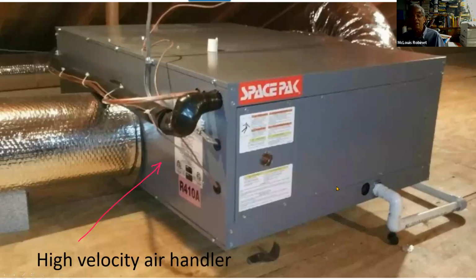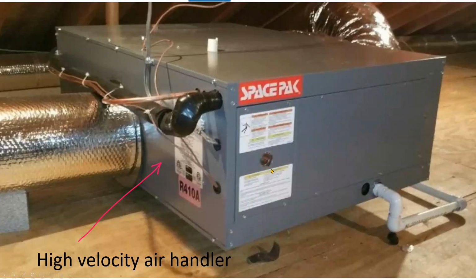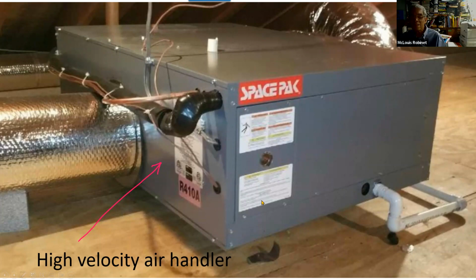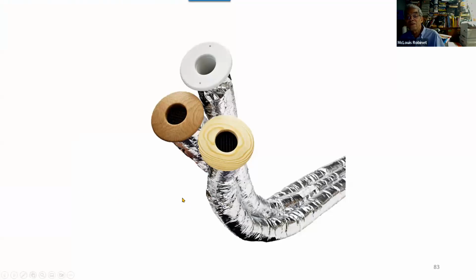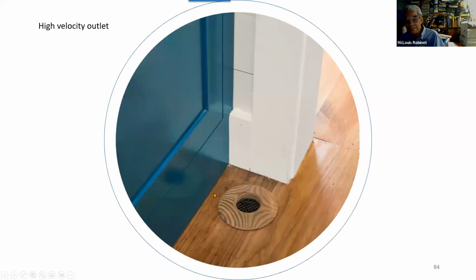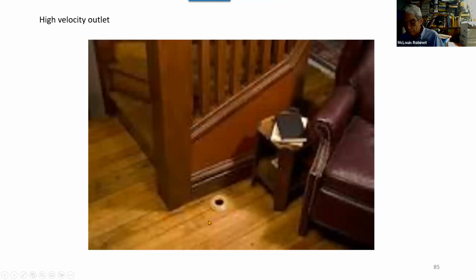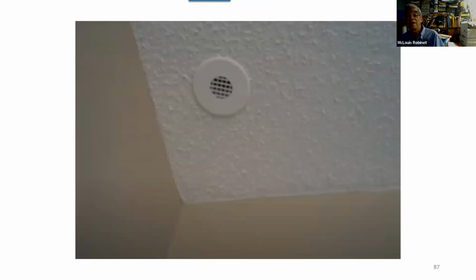An alternative that people don't talk about is to switch to what's called a high velocity air handler. So instead of having to remove all of your radiators and replace them with air handlers, you could switch to a high velocity air handler, drive this with an air to water heat pump, and use very small tubing. Say these are 2.5 inches in diameter. You may have seen some of these, in the floor or the ceiling. The air comes out at a high velocity, but it's very quiet. The way it's designed, it washes off the wall and you get perfect mixing. So it's a really pretty efficient system, and that's something one might consider.